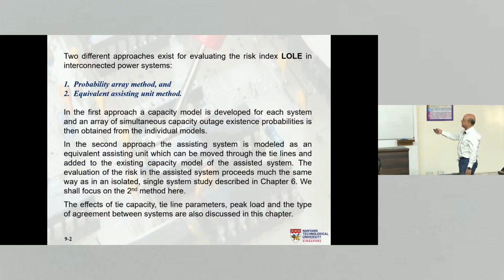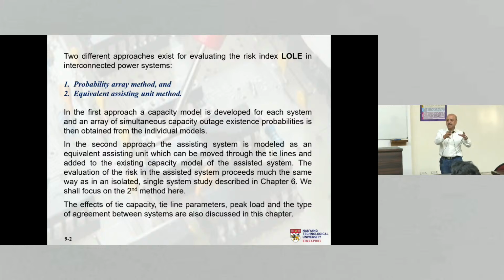The second method is equivalent assisting unit method. So we will see how much support system B can provide to system A, for example. And we will then model the support from system B as another generating unit, right? And by now we know how to add a generator to our system, right? So we call that equivalent assisting unit method. The assisting unit is modeled as another equivalent generator, and then we treat this together with our system, and then we redo the calculations and we find how the reliability has improved.